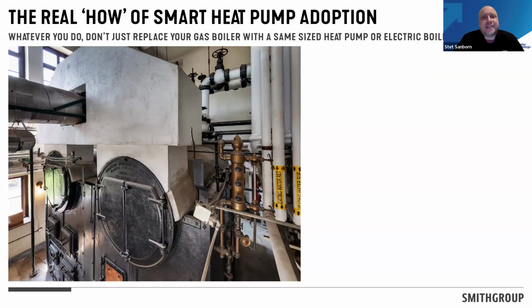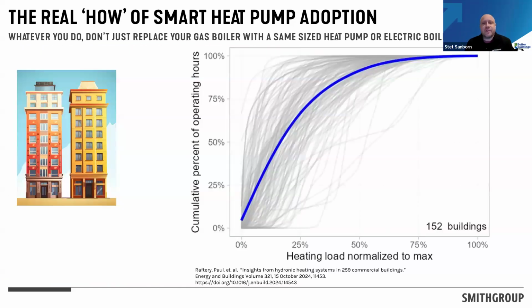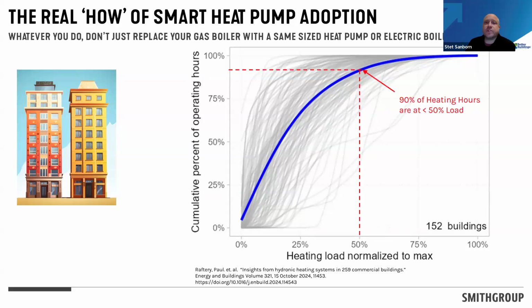Let's talk about why. This is from a recent survey of almost 260 buildings completed by the Center for the Built Environment. This curve shows, on the y-axis, the percent of operating hours the existing boilers were running, compared to the x-axis, the normalized heating load versus the max size of the equipment. Across all those real-life buildings, 90% of the hours the building was operating at less than 50% of nameplate capacity.